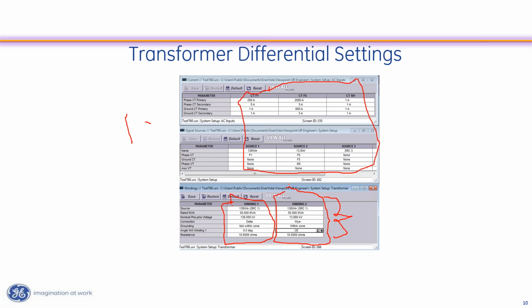So the settings on the UR are very much like settings for the 8 series. But basically, this first setting here, the MVA of the winding. The relay will use that to calculate a reference winding for phase compensation, right? And that winding will be the reference for all of the other calculations.